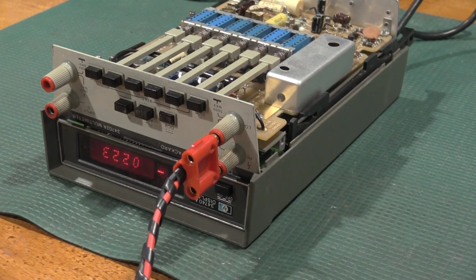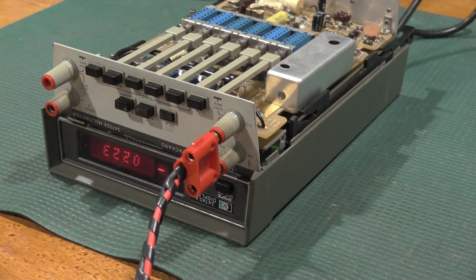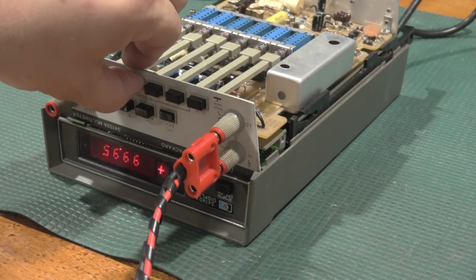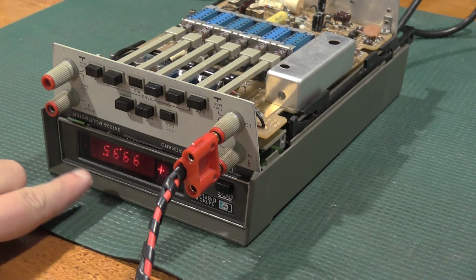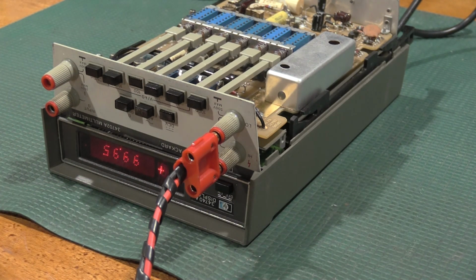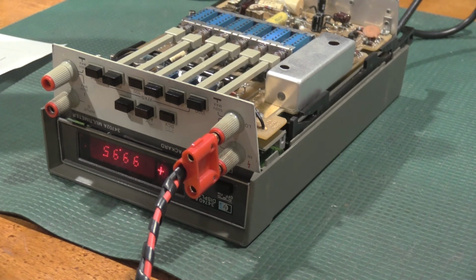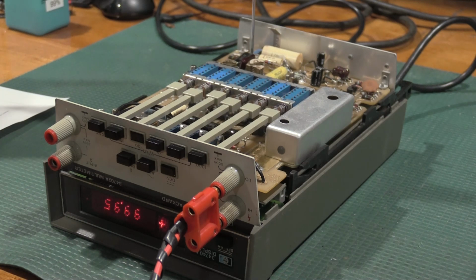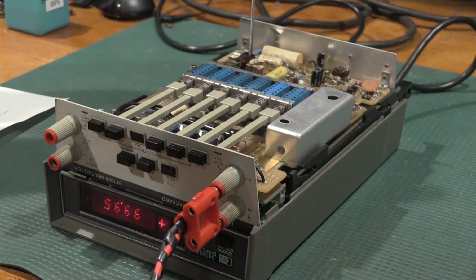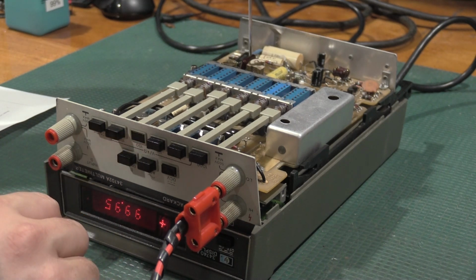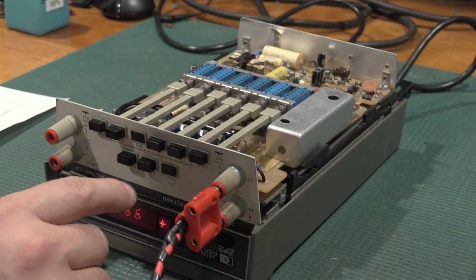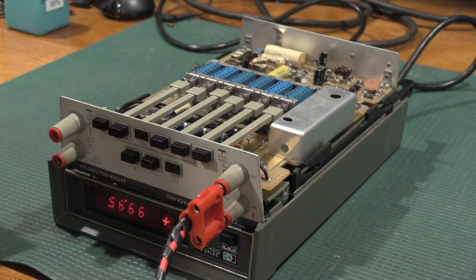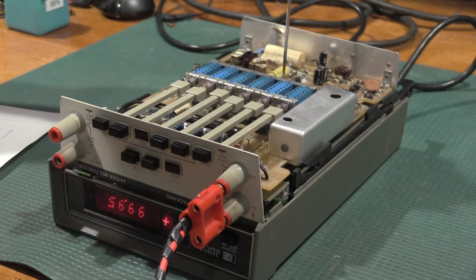Okay, when I turn on the standard, the 100 volts should be applied to the test terminals. Here we go. Looks like that needs a little bit of adjustment. 100-volt DC adjust is this potentiometer right here. That's the 1000-volt pot. Whoops. Wrong pot. That's okay. I need to adjust the 1000 volts next.